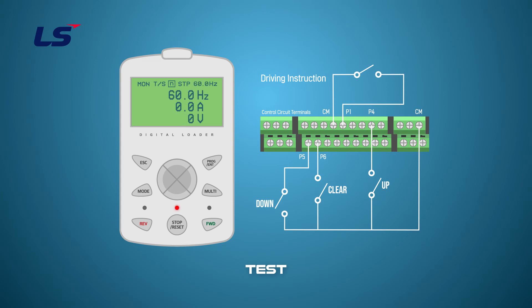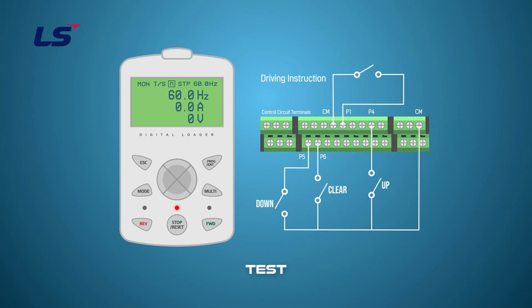After turning the Up off, turn on the FX again to check if the frequency is stored. You can see that the drive is accelerating to 60 Hz even when the Up operation is not turned on. To delete the stored frequency, turn on and off the digital input programmed to clear Up and Down. Then turn on the FX digital input again and check if the saved frequency has been deleted. You can see that it does not accelerate at 0 Hz.